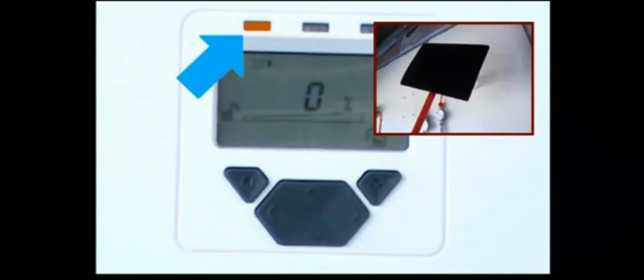To perform the trouble test, completely cover the receiver using non-reflective material, taking less than 2 seconds to do so. After the delay to trouble time, the system controller indication LED and relay pair corresponding to this receiver will now be in a trouble condition. Uncover the receiver to return the system to normal operation.